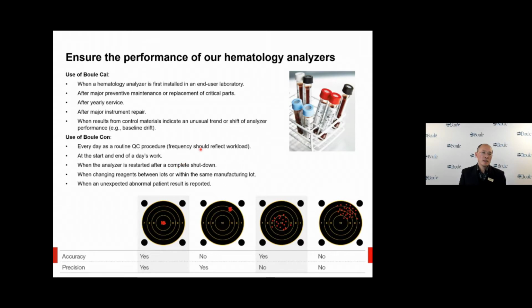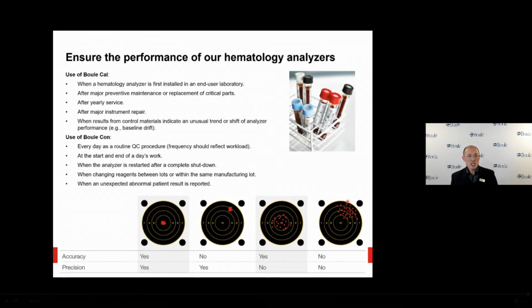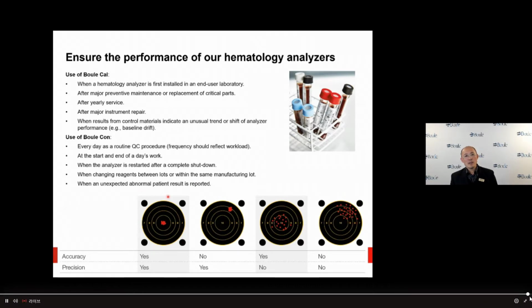It is to check the performance of the instrument, and in case the result is unstable, the user can run control blood multiple times, and then in the instrument menu choose these samples to do statistics, either on the instrument menu or with an Excel sheet, to calculate the precision level of this measurement. And in case the precision is not good, then troubleshoot the reason.